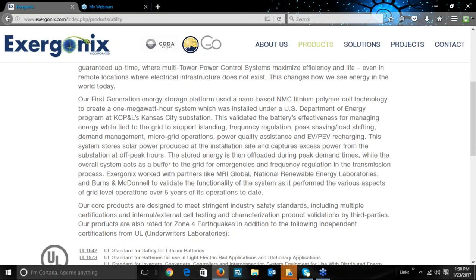Our first generation energy storage platform used a nano-based NMC lithium polymer cell technology to create a 1 megawatt hour system, which was installed under a U.S. Department of Energy program at KCP&L's Kansas City substation. This validated the battery's effectiveness for managing energy while tied to the grid to support islanding, frequency regulation, peak shaving, load shifting, demand management, microgrid operations, power quality assistance with EV and PEV recharging. This system stores solar power produced at the installation site and captures excess power from the substation at off-peak hours. The stored energy is then offloaded during peak demand times, while the overall system acts as a buffer to the grid for emergencies and frequency regulation in the transmission process.